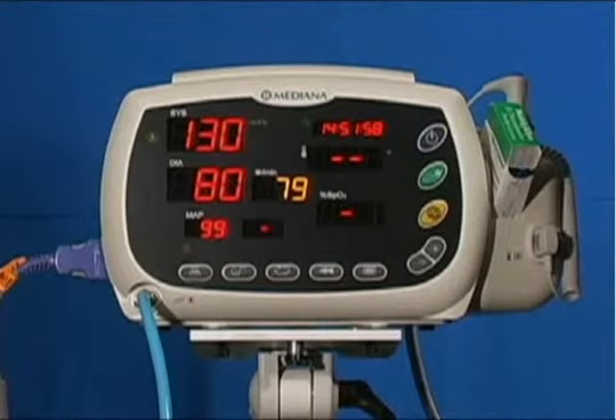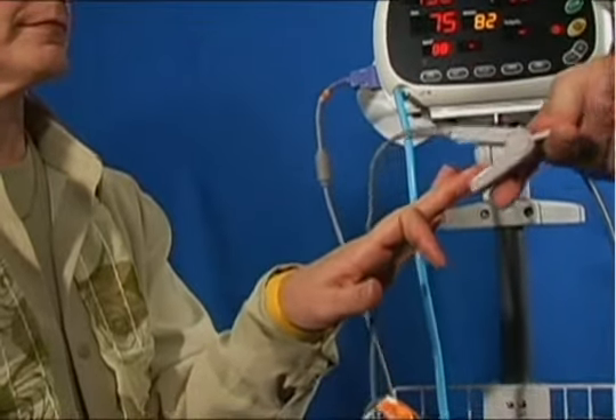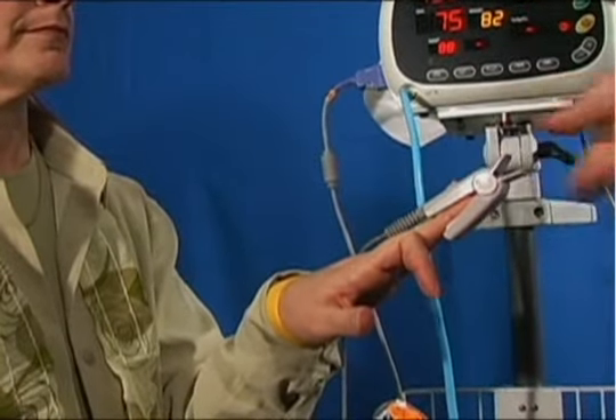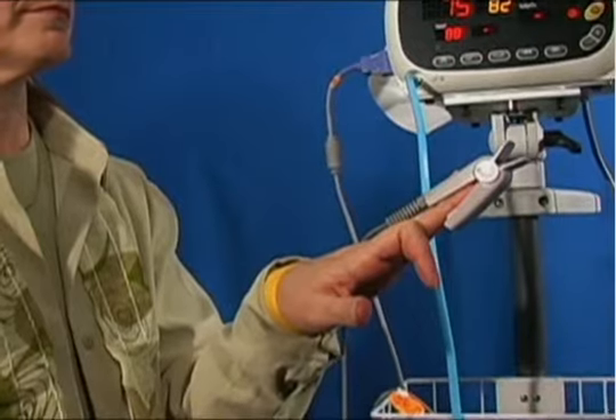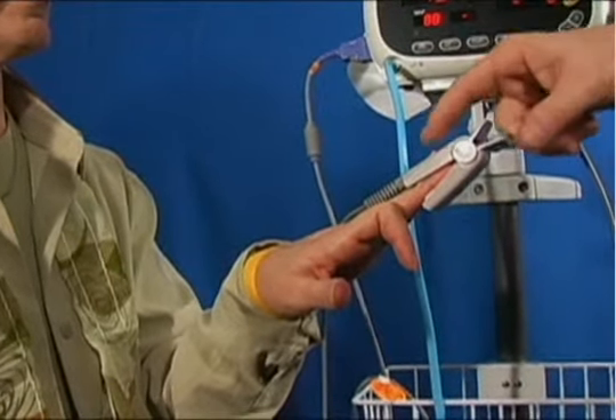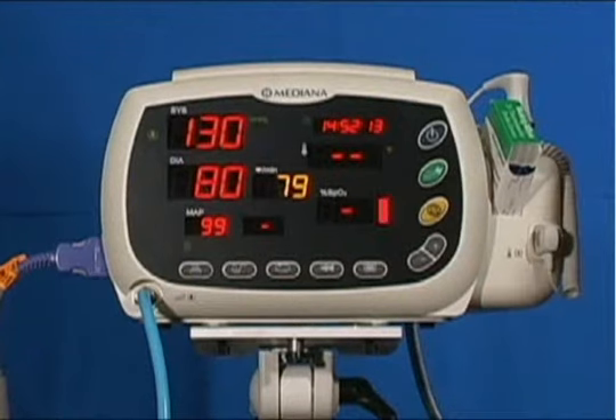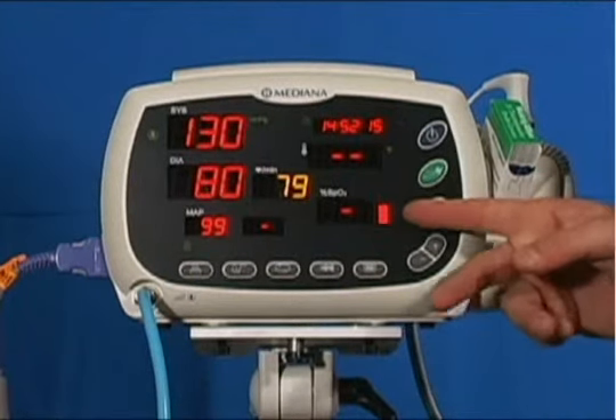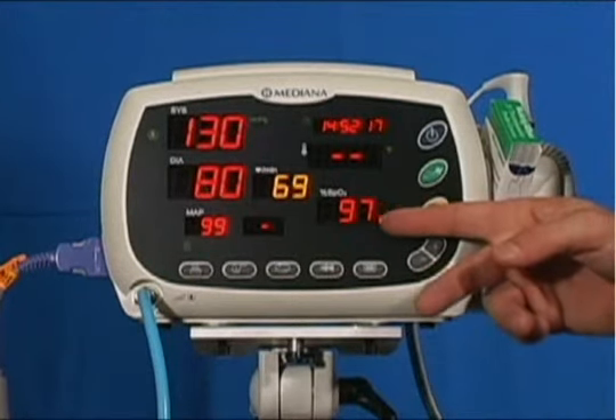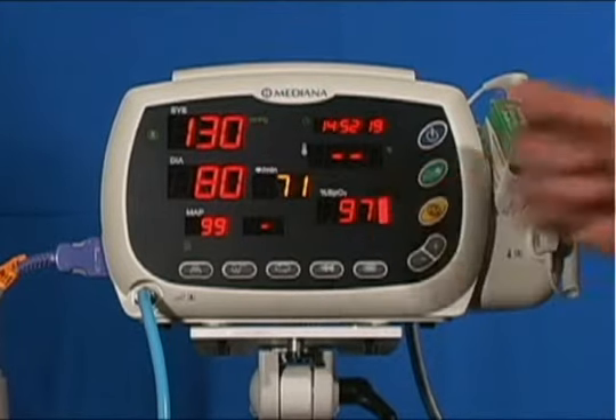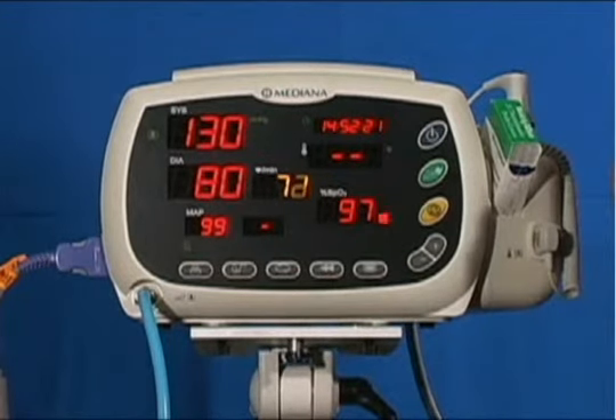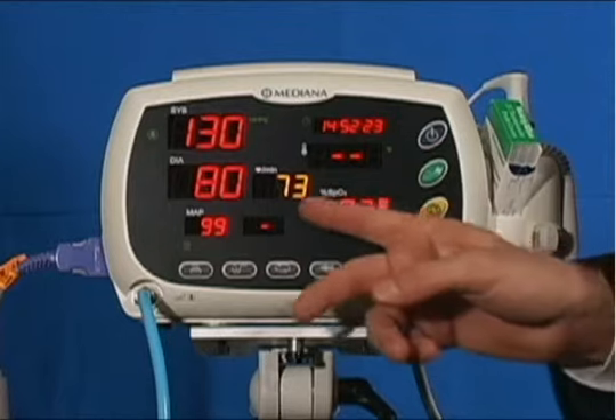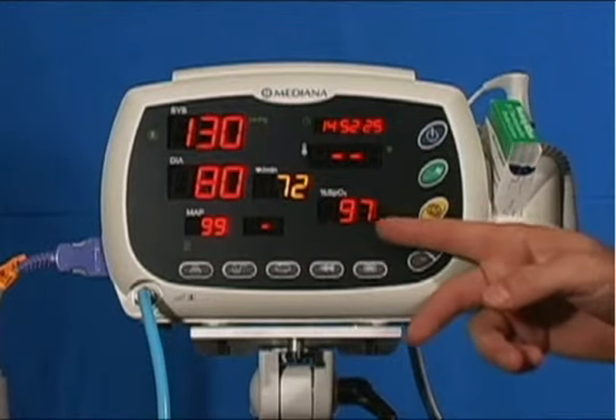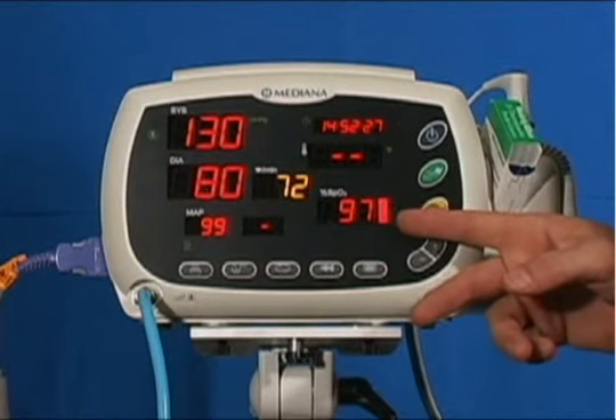The next parameter we're going to hook up is pulse oximetry. So I'm going to use my reusable pulse ox sensor. This is the Nellcor Oximax technology. The best place to get a reading on your patient is your middle finger of your left hand. So we apply the probe. Monitor does a pulse search here, and then the SpO2 comes up. Now I get a continuous heart rate on the display, where before when I was just doing blood pressure, I got a one-time heart rate. And now it's continuous based on the pulse.